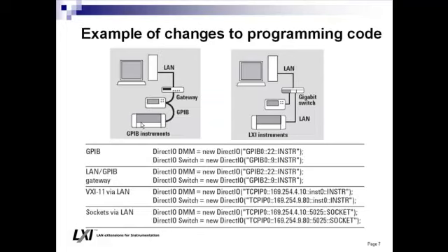Here are examples of changes you would need to make to your programming code. With GPIB, you have VISA designators — descriptors of how you actually talk to that instrument — and various I/O routines to configure communication. Whether moving from a gateway-operated GPIB subsystem or a direct GPIB subsystem to fully LAN-based instruments, you simply take those same VISA descriptors and substitute the equivalent descriptor for the LAN-based instrument.